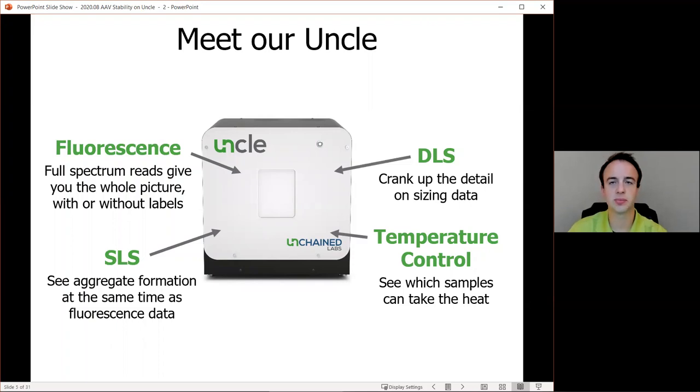DLS is dynamic light scattering and allows for detailed measurements of size and size distribution. These three detection methods can be operated isothermally, at room temp, or across a heat ramp designed to thermally stress samples and see which ones can take the heat. UNCLE is able to deliver results in aggregation with two different looks at viral capsid stability in about two to three hours with nine microliters of sample for up to 48 samples at a time.